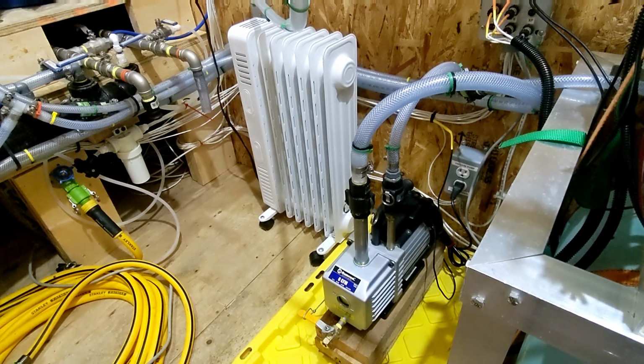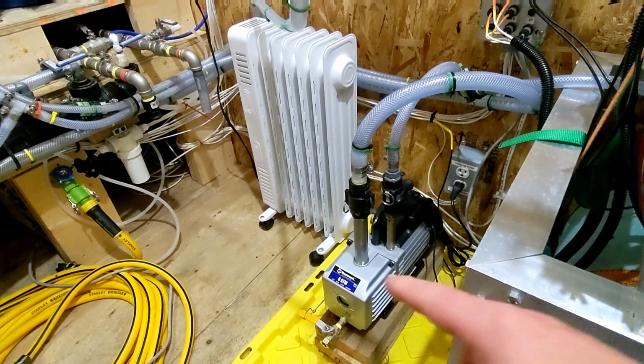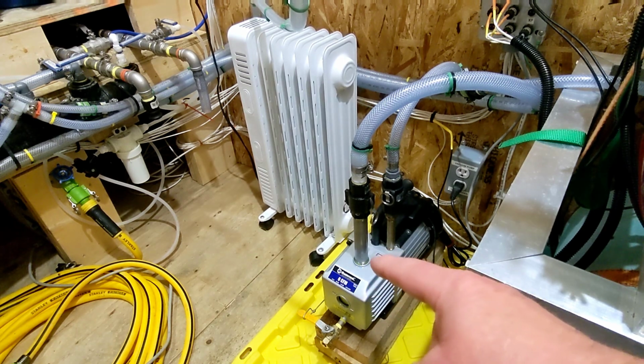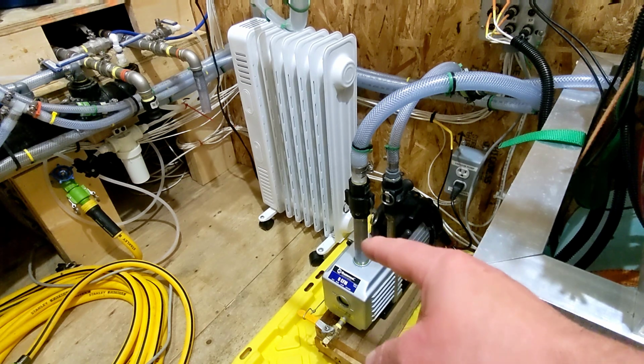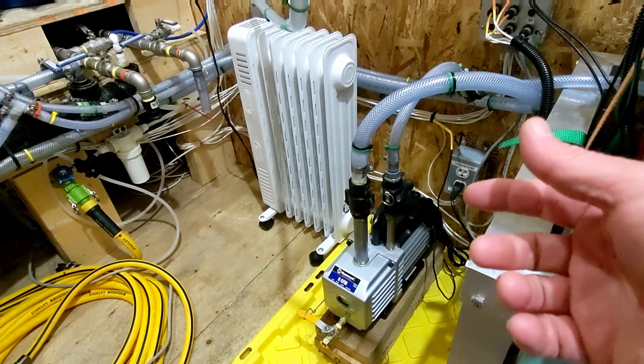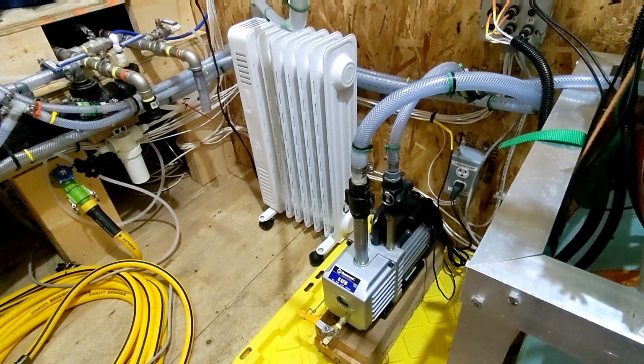And just a couple of other things that we've got going on in here. So this right here is a Mastercool 90066A vacuum pump. It does 6 cubic feet per minute. It will produce about 29 inches of mercury of vacuum, which is a moderate vacuum. That's been running my system for years. It's a serviceman's pump, so it's only intended to be run for a few minutes at a time while they do service. I run it 12 to 16 hours a day for weeks at a time. I figure it's got several thousand hours of service on it. So it has been an absolute workhorse for me.